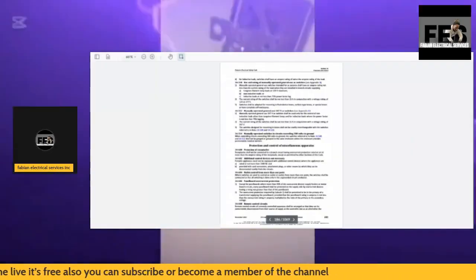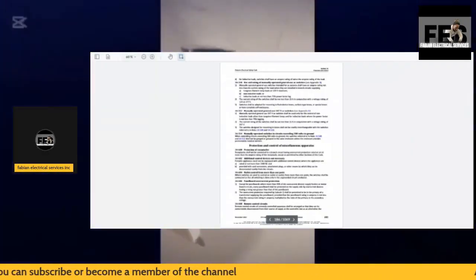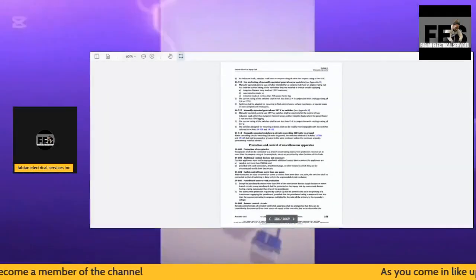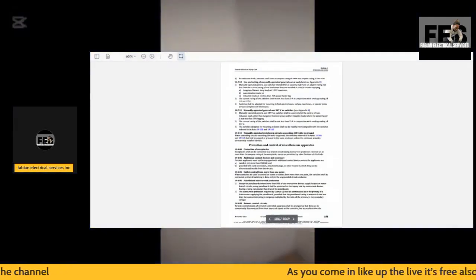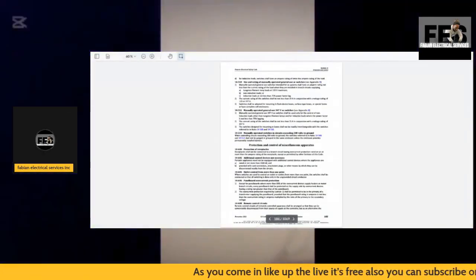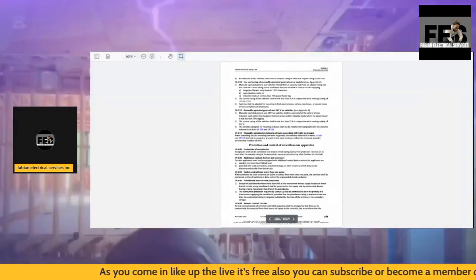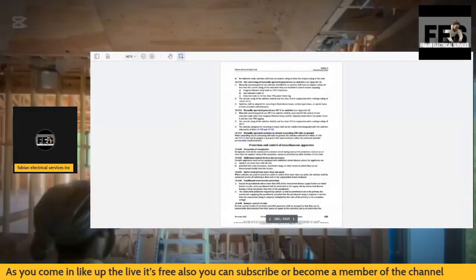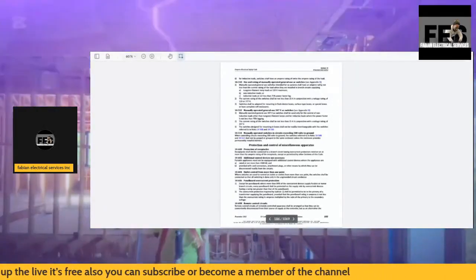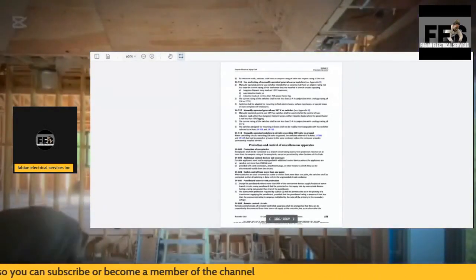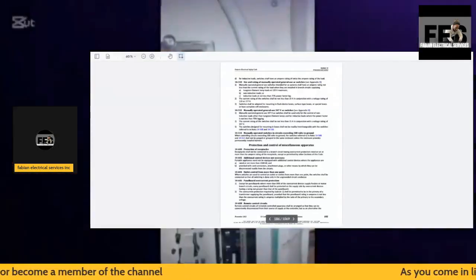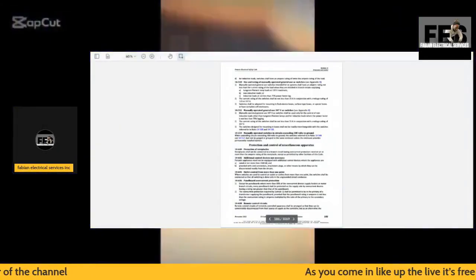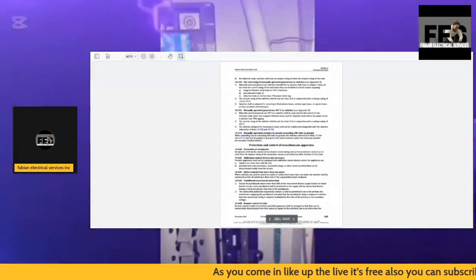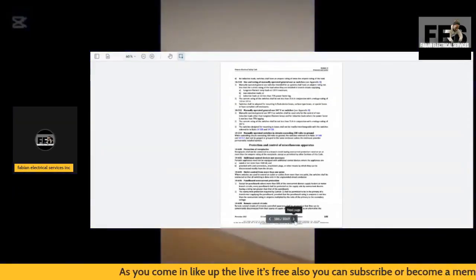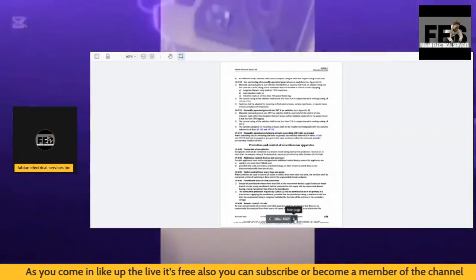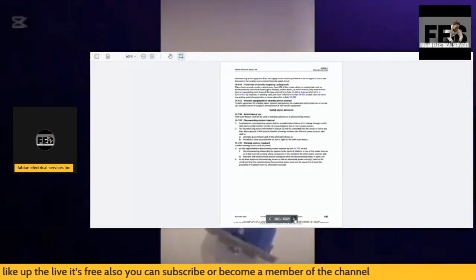So again, sub-rule 1 says except for panel boards where more than 90% of the overcurrent devices supply feeders or motor branch circuits, every panel board shall be protected on the supply side by an overcurrent device having a rating not greater than that of the actual panel board. So that's one of the rules that I want to touch base on.